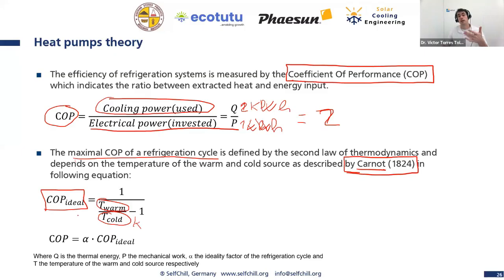COP ideal, COP Carnot. Okay, and I can tell you, this COP Carnot will always be higher than the COP we have in reality. And this depends on the ideality factor of our heating systems, or our cooling systems, sorry. And I can tell you heat pumps go between 20 and 30% of the ideal COP. So if Carnot is telling us we can get a COP of 10, and then we have a 25% ideality factor, then our real COP will be 2.5.